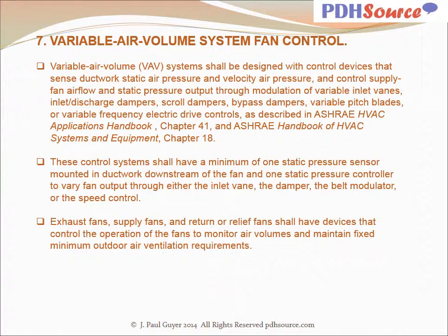These control systems shall have a minimum of 1 static pressure sensor mounted in ductwork downstream of the fan and 1 static pressure controller to vary fan output through either the inlet vane, the damper, the belt modulator, or the speed control. Exhaust fans, supply fans, and return or relief fans shall have devices that control the operation of the fans to monitor air volumes and maintain fixed minimum outdoor air ventilation requirements.